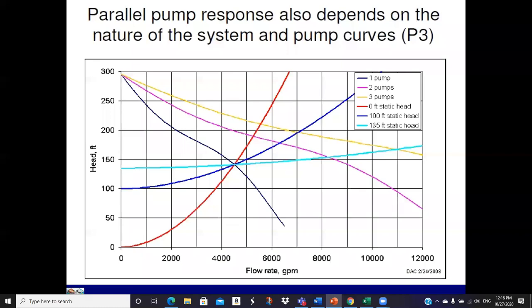And just a quick review. What we're looking at here is our three system curves. The red one is all frictional. This one, what is that, dark blue? I'm a little colorblind, but at any rate, we have about 100 feet of static head, and then we're frictional from there. And then this light colored blue-green one, aqua maybe, looks like that's 130 feet of static, and just a little bit of frictional head as we increase flow. So these are all drawn through the same operating point. I think this is 130, 140, 141 feet of head, I can't remember the number. It's a little short of 150 feet at 4,500 GPM. And so three different types of systems.